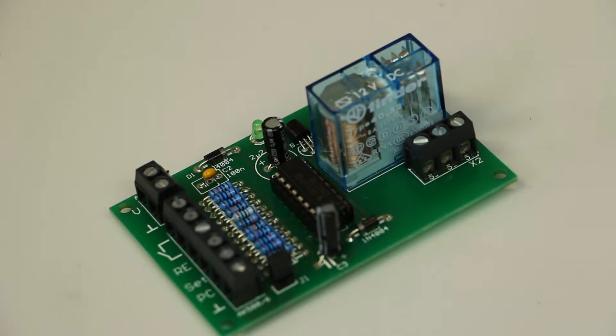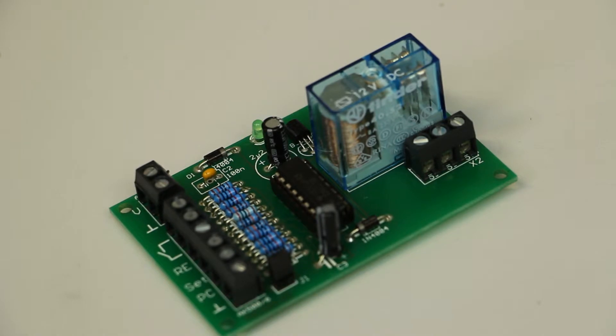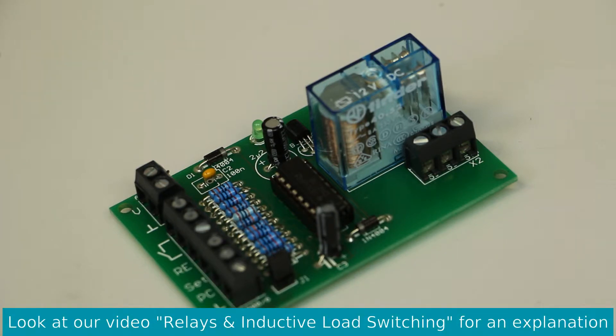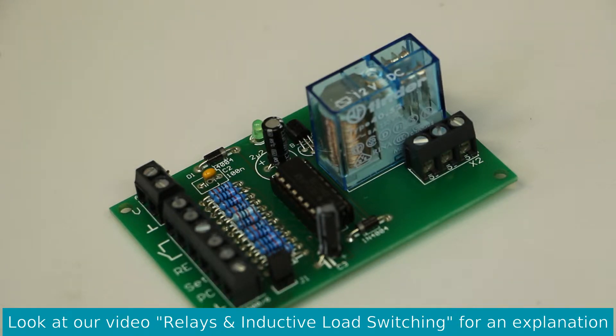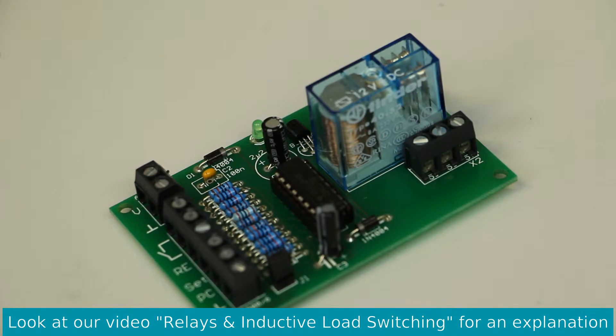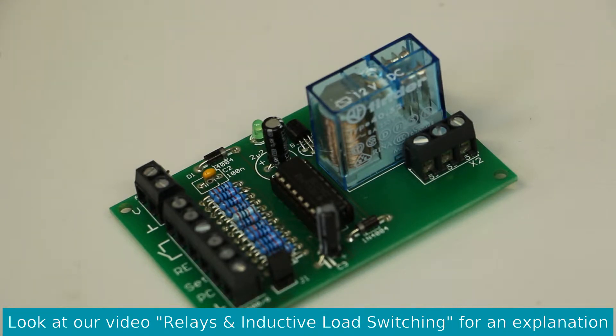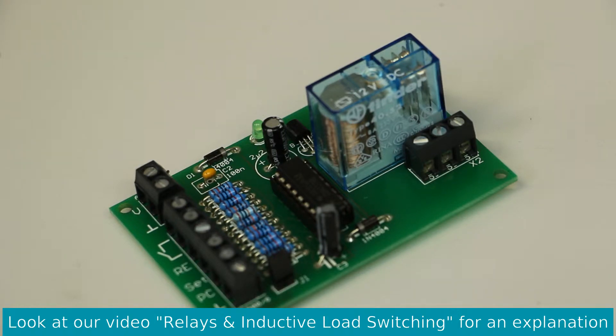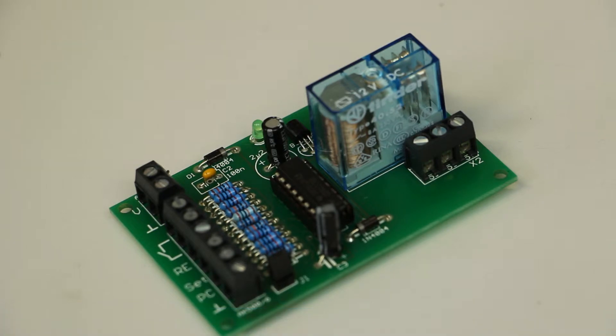But there's another thing you should be aware of. This spec only applies to resistive loads, which means a heater or something like that. When you want to switch inductive loads, the power rating is much lower. For example, if you're switching a motor with this relay, it's only specified for up to 300 watts switching capacity at 230 volts mains voltage. So there's a big difference between what it can switch with resistive loads or with inductive loads.